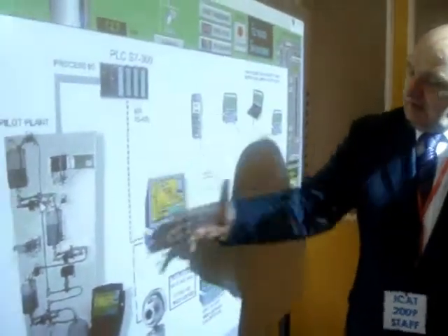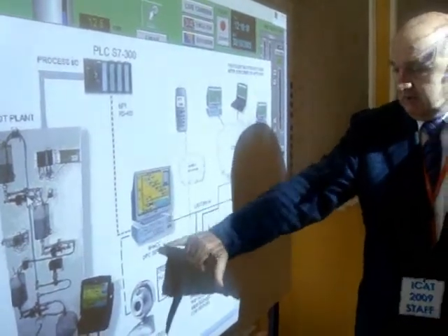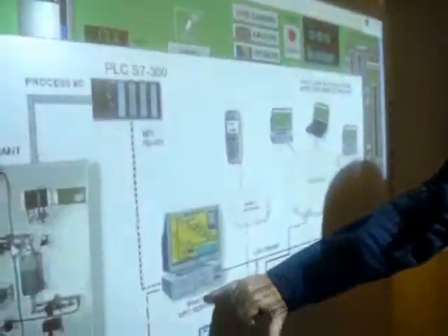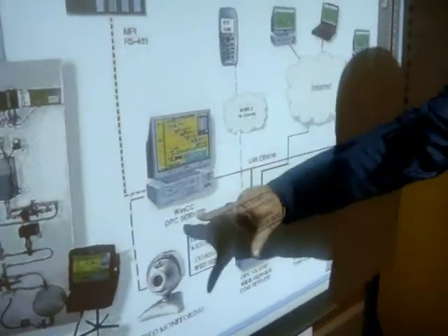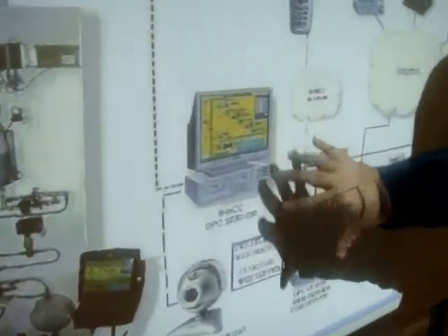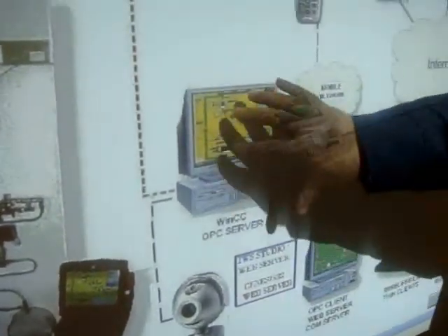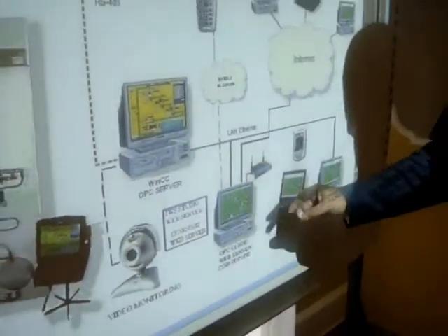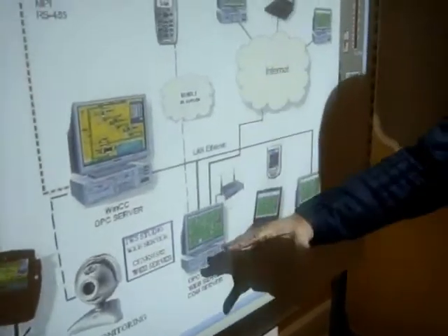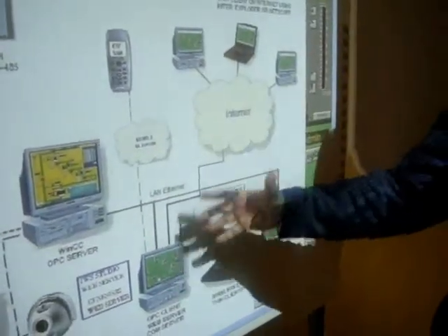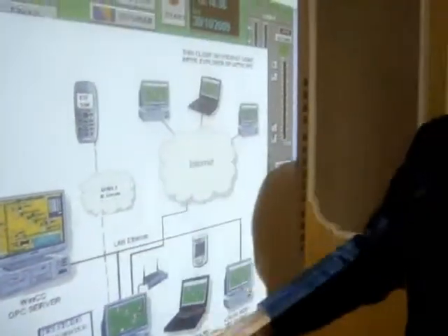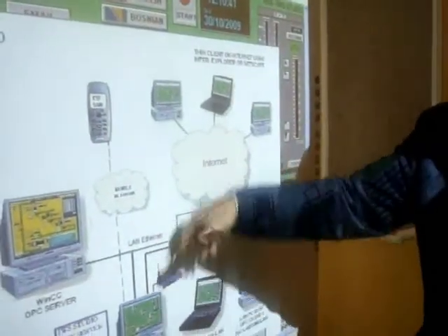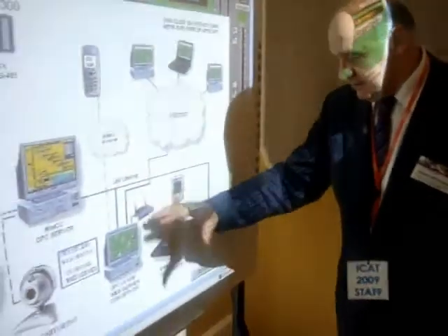Now this PLC is connected to a PC, which is running WinCC control center, that's HMI software from Siemens, and then we are using OPC protocol and communication to transmit all these real-time data from the PLC to a second PC, which is now putting it all on the web, on the internet.